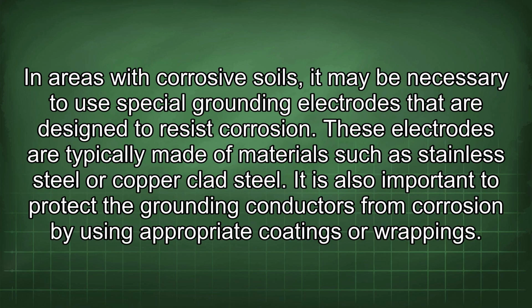In areas with corrosive soils, it may be necessary to use special grounding electrodes that are designed to resist corrosion. These electrodes are typically made of materials such as stainless steel or copper-clad steel. It is also important to protect the grounding conductors from corrosion by using appropriate coatings or wrappings.